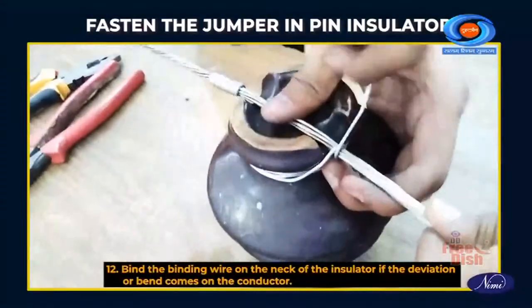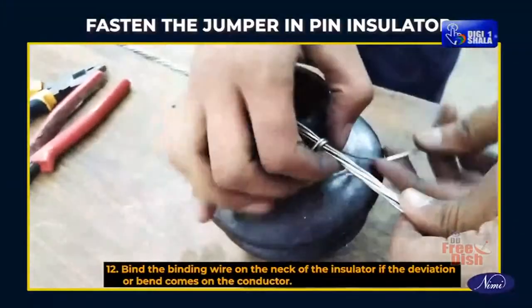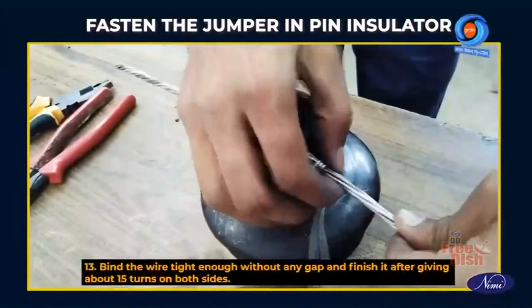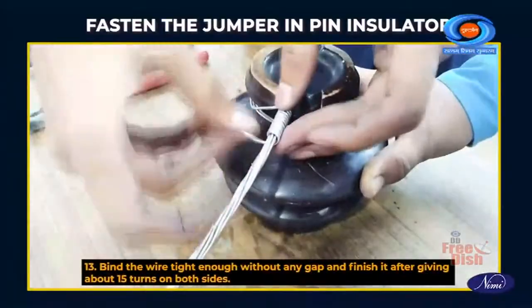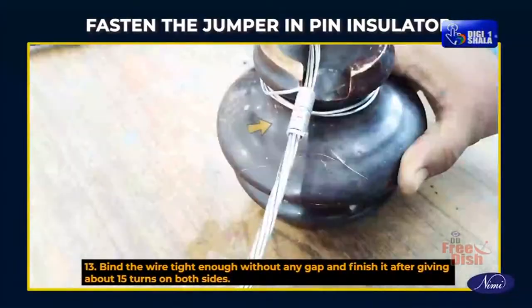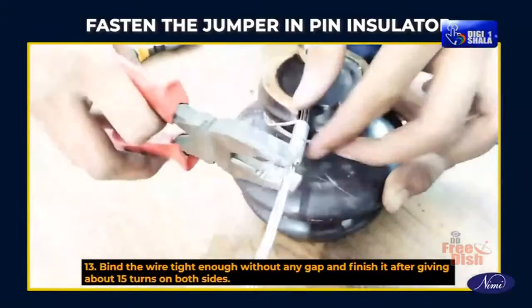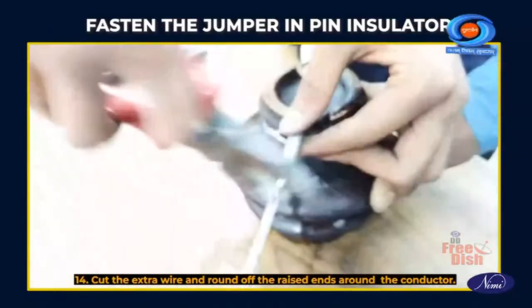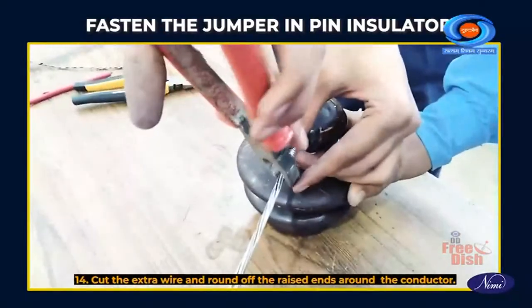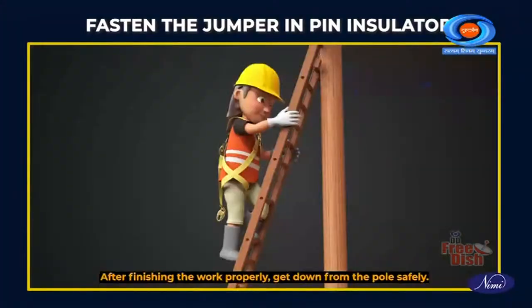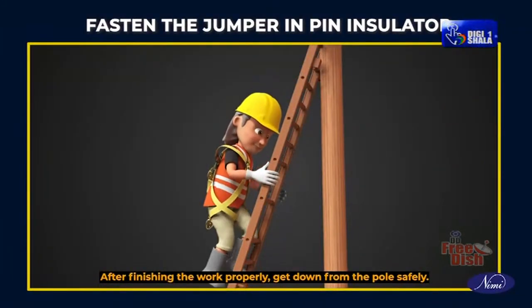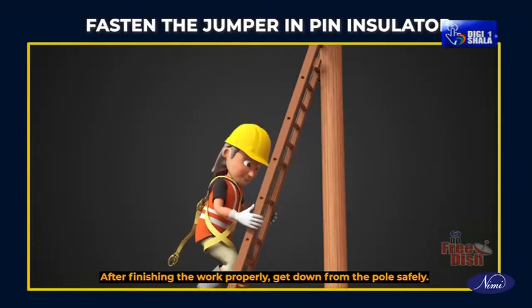Bind the binding wire on the neck of the insulator if the deviation or bend comes on the conductor. Bind the wire tight enough without any gap and finish it after giving about 15 turns on both sides. Cut the extra wire and round off the raised ends around the conductor. After finishing the work properly, get down from the pole safely.